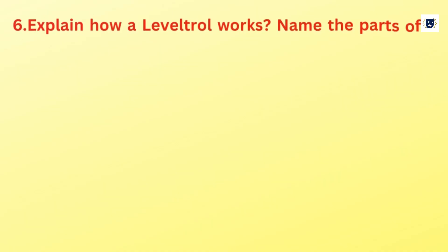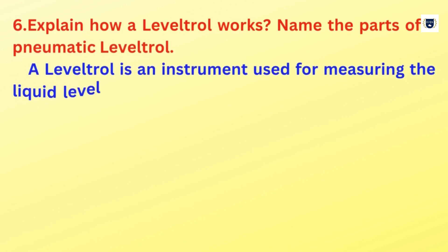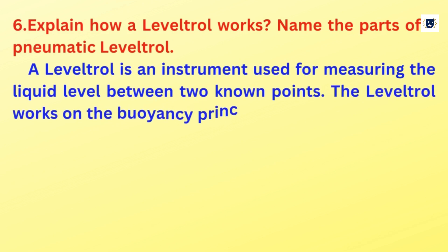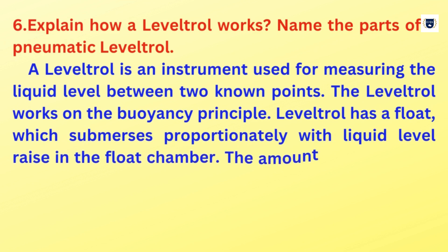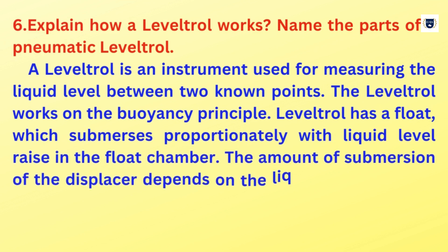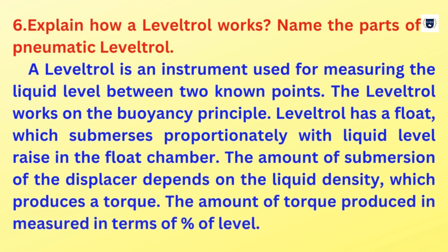Explain how a Leveltrol works. A Leveltrol is an instrument used for measuring the liquid level between two known points. The Leveltrol works on the buoyancy principle. It has a float which submerses proportionately with liquid level rise in the float chamber. The amount of submersion of the displacer depends on the liquid density, which produces a torque. The amount of torque produced is measured in terms of percent of level.